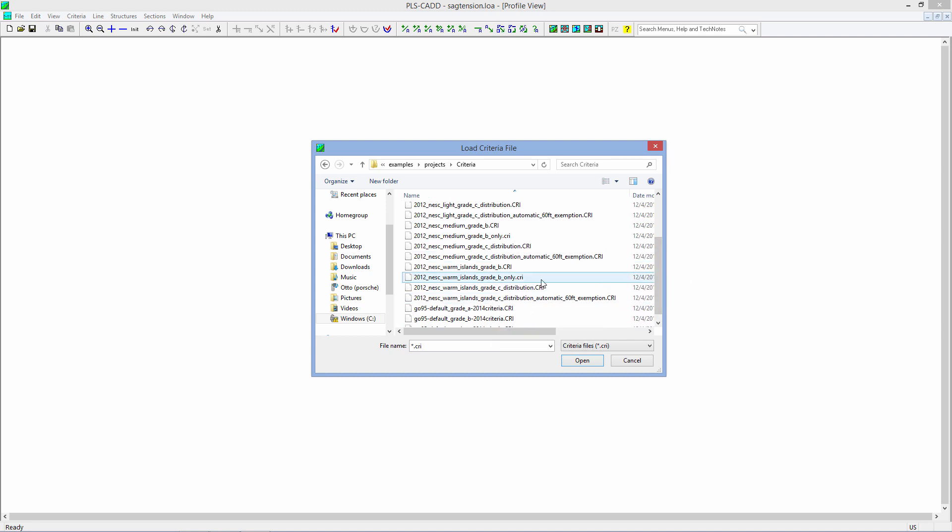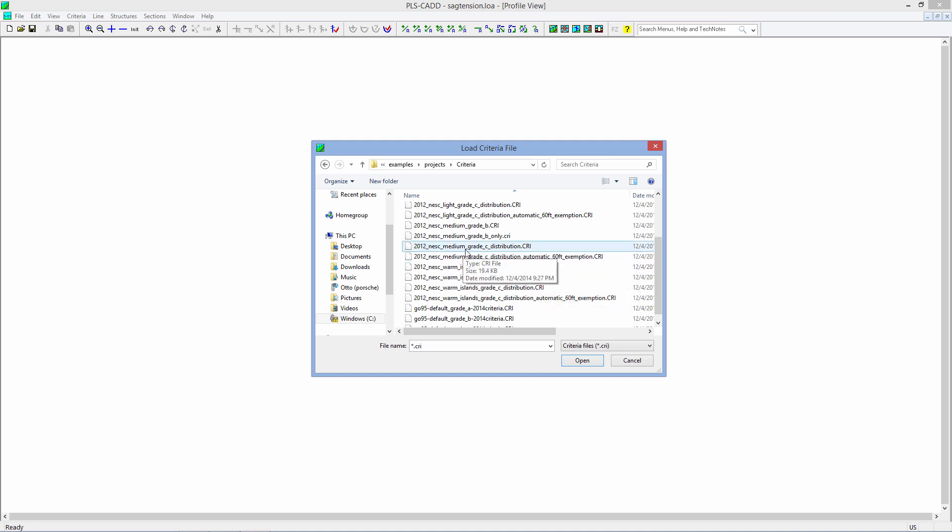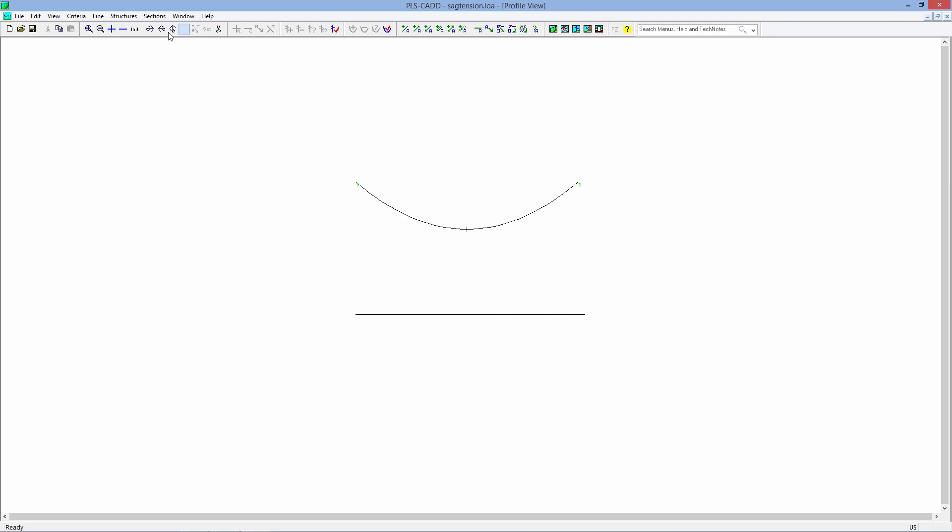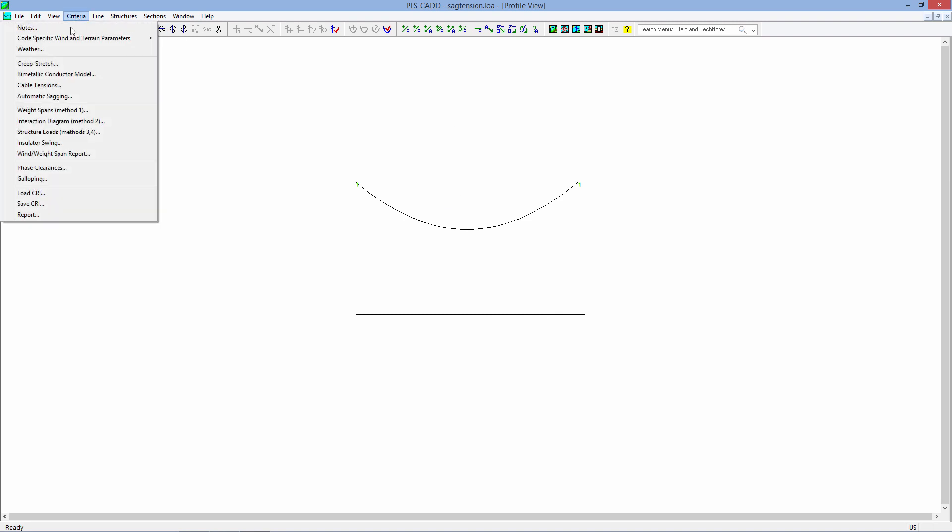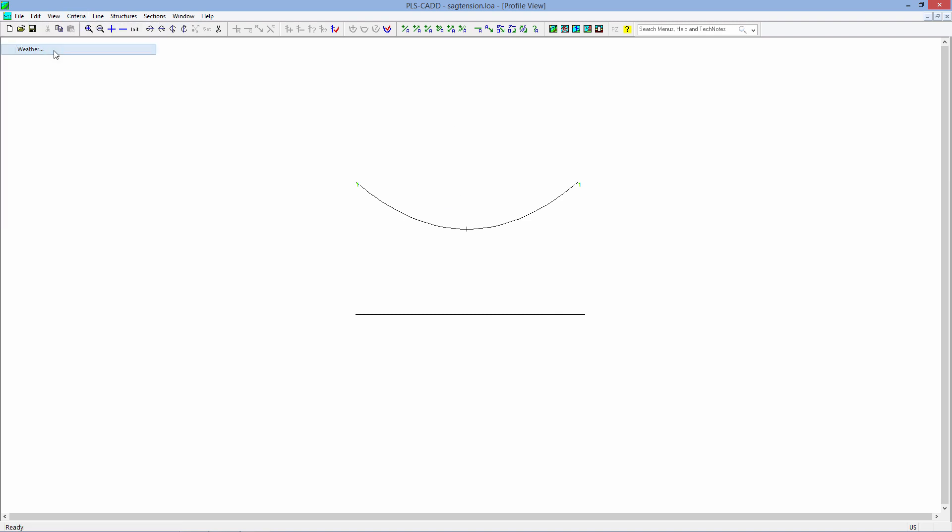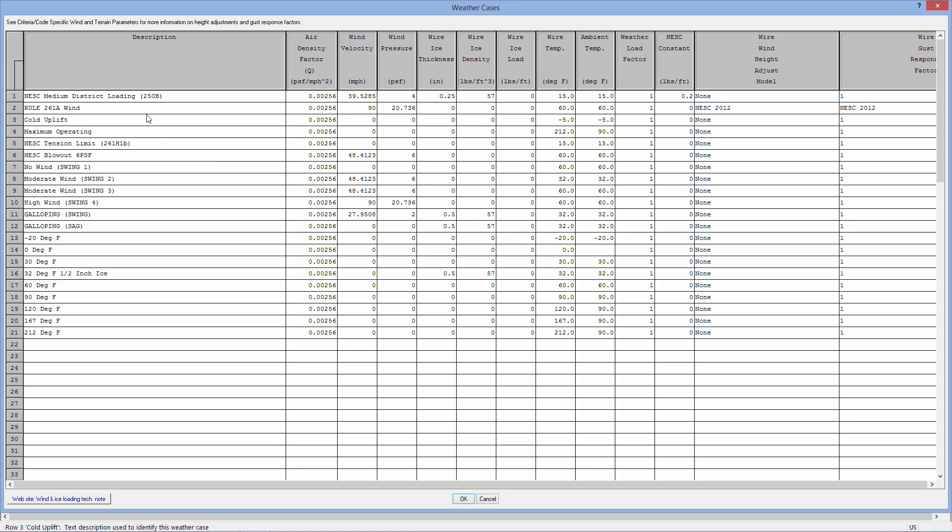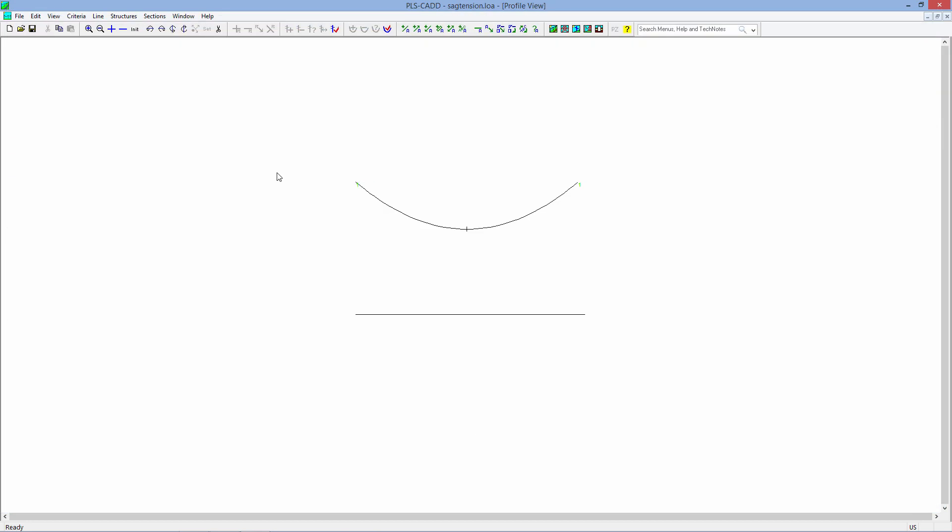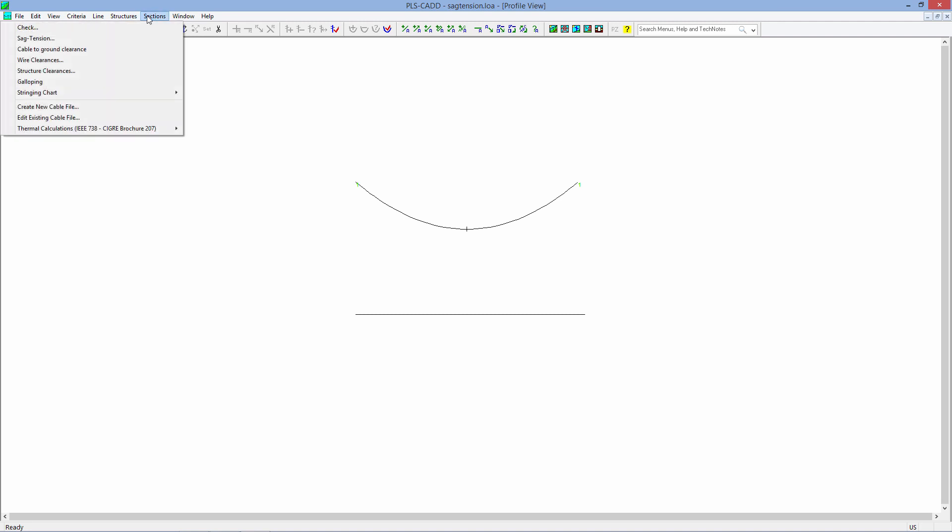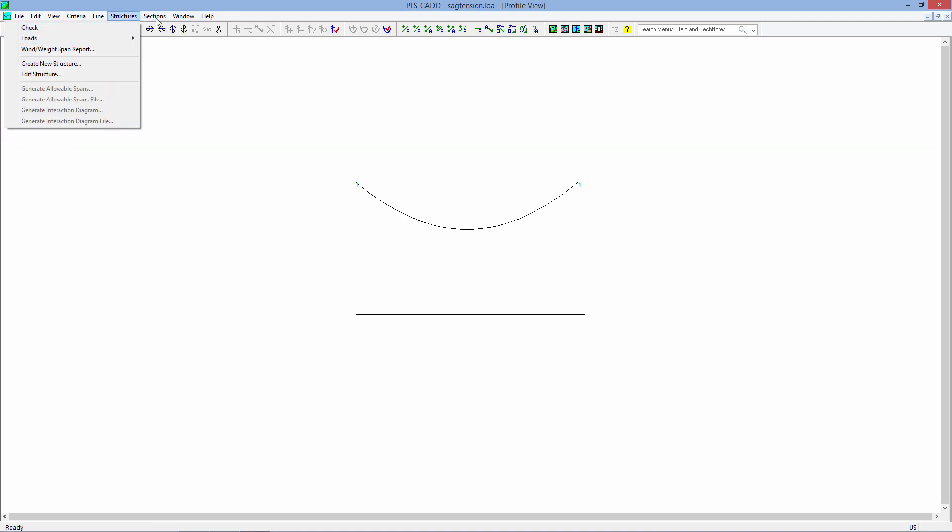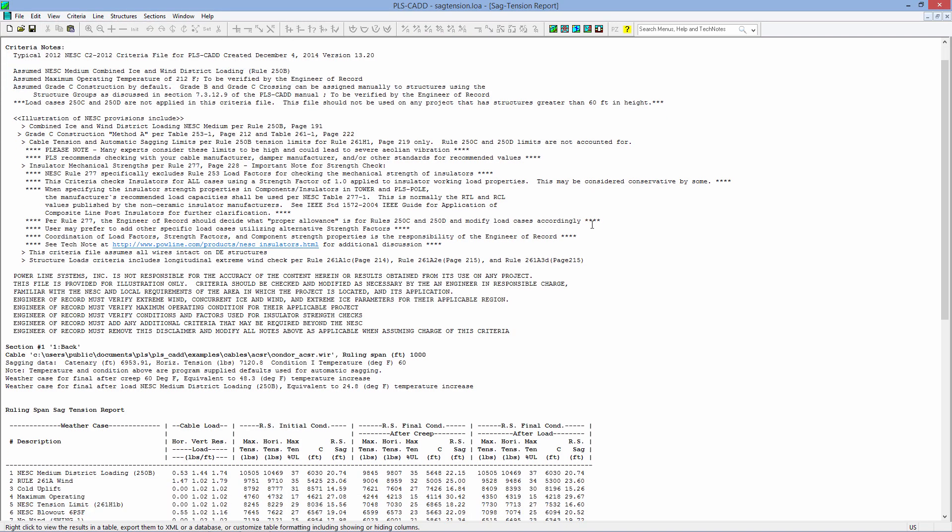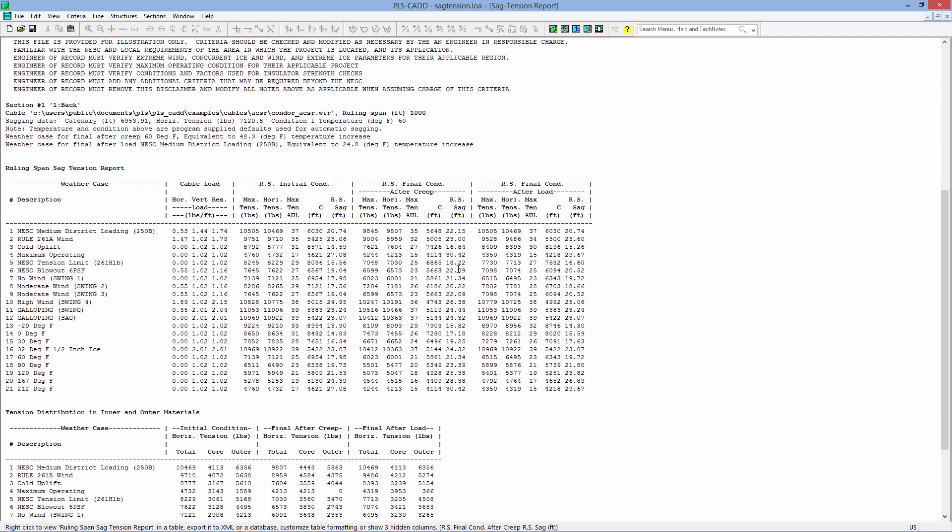But if I were to go in here and just choose the basic NESC medium, grade C, distribution only, and we say okay, there is no reference to rules 250C and D or any of the other design criteria that might apply to your structures that are above 60 feet. And, of course, if you do a section sag tension, we'll get a report that only has that specific information without reference to 250C or 250D.